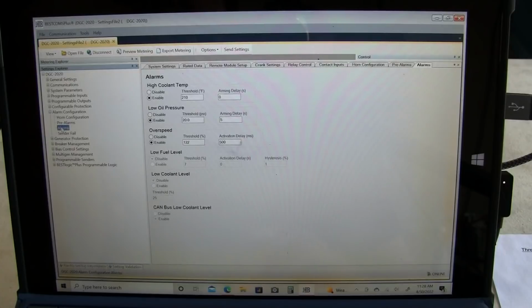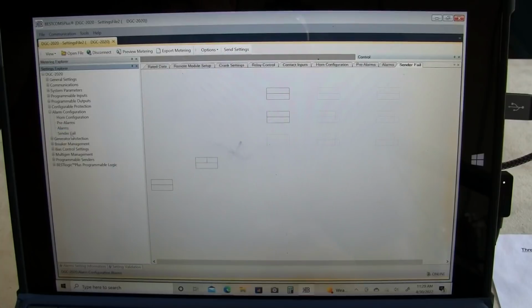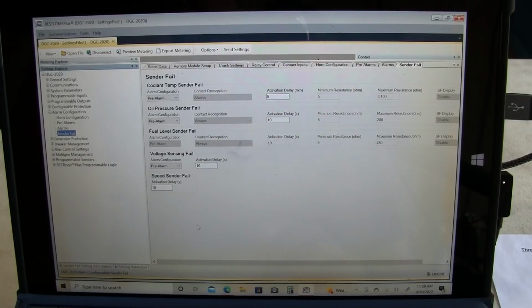Let's see, alarms. Alarms is pretty simple. High coolant temp. It'll shut the genset down if the coolant temp hits 210. Low oil pressure. It will shut the engine down if we hit 20 pounds of oil pressure. Overspeed. If the unit exceeds rated speed or 100% speed by 22%, it will shut the genset down after half a second. Low coolant level is disabled. CAN bus low coolant level. Well, this is in a non-electronic engine, so we have no CAN bus. And sender fail. I don't know if I've set this one yet.